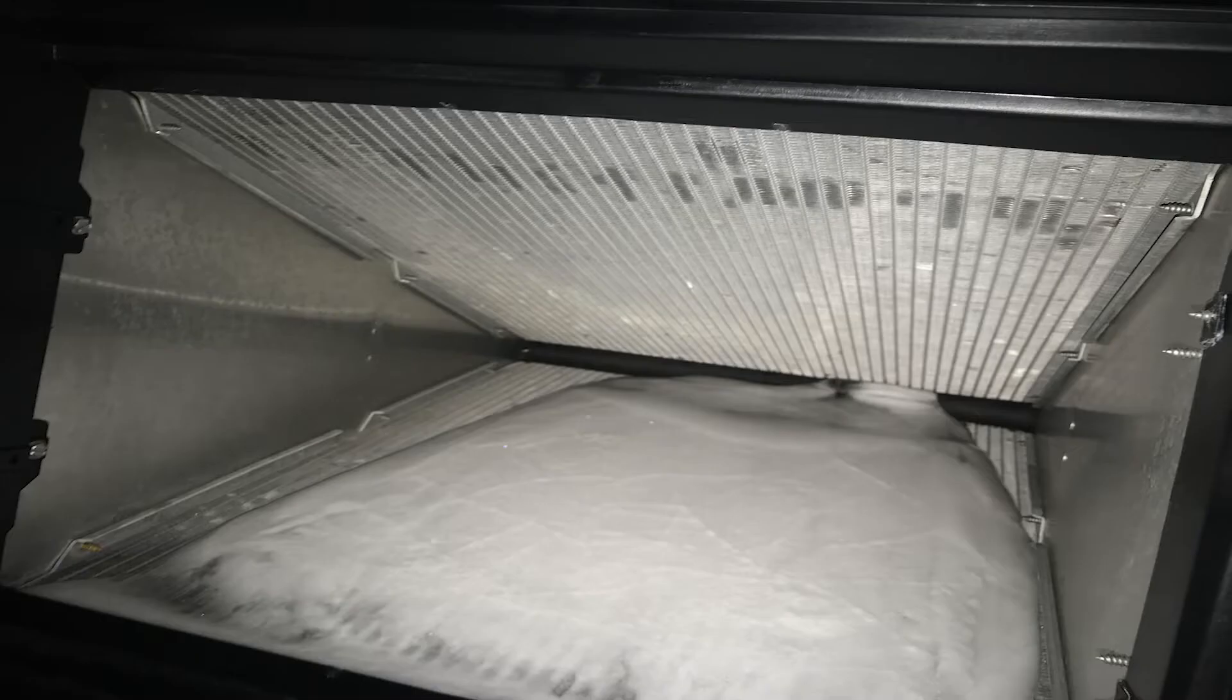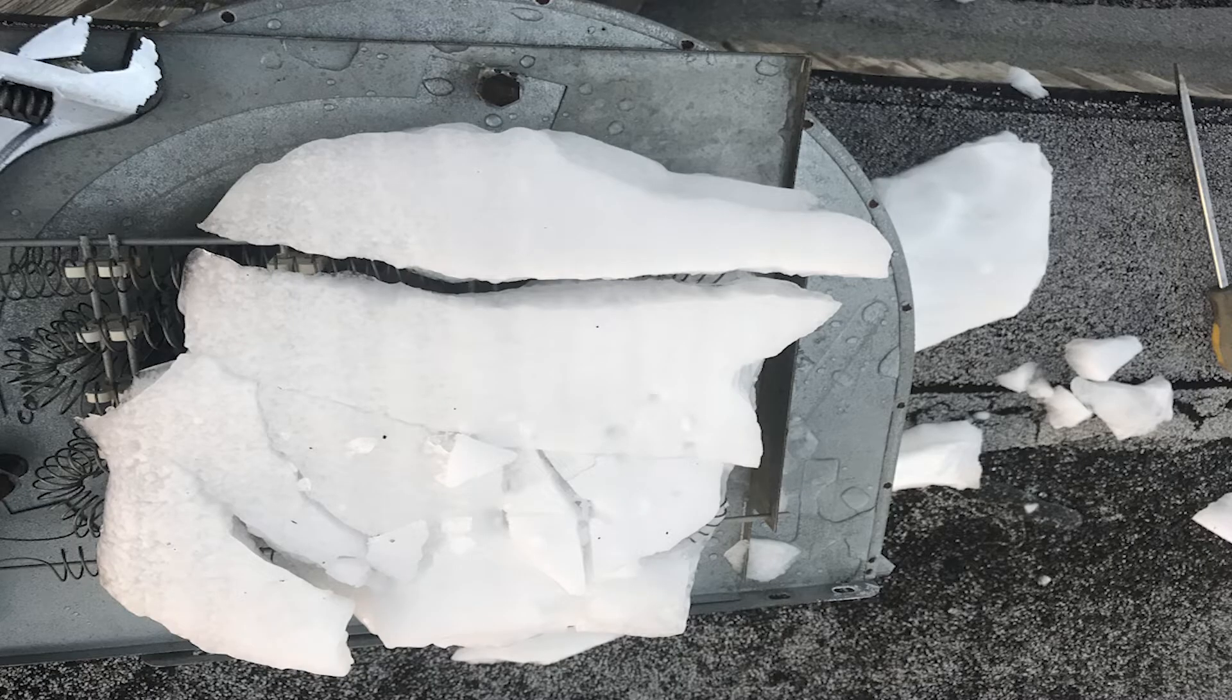Instead of the air condensing on that coil as water, it starts to condense there as ice. It starts to build up ice because that coil is so cold, either because of a lack of airflow or a lack of refrigerant. The pressure is much lower because there's no refrigerant in there, and so the temperature also gets a lot colder, and it starts to condense as ice on your coil.